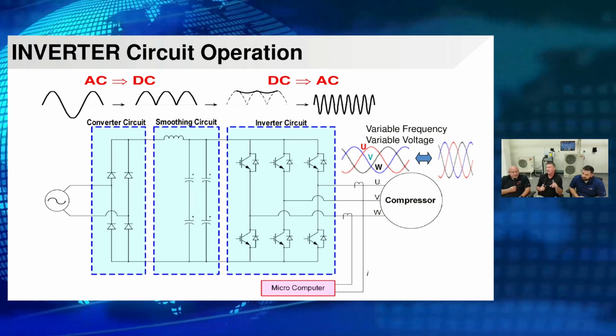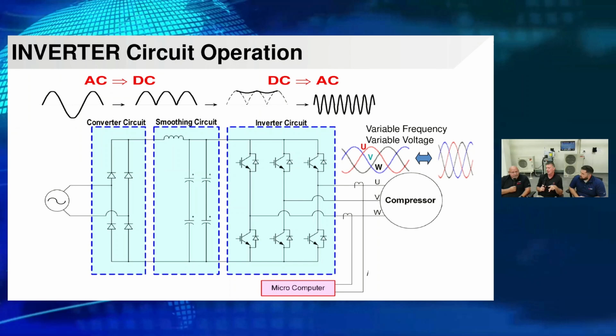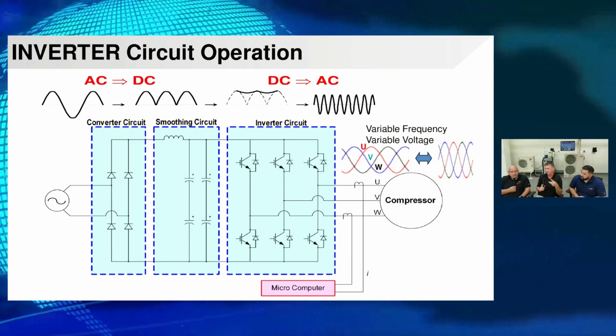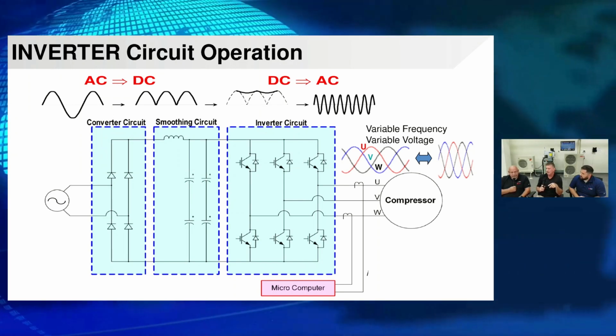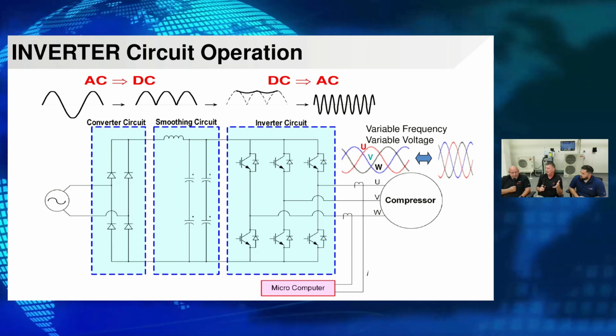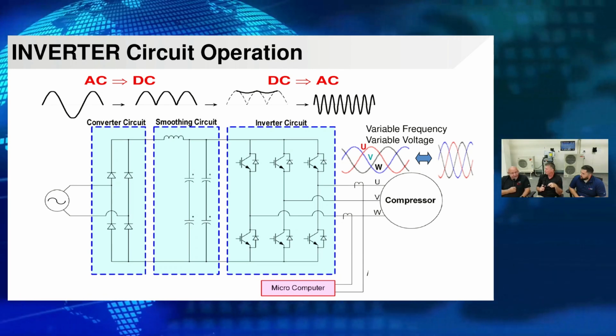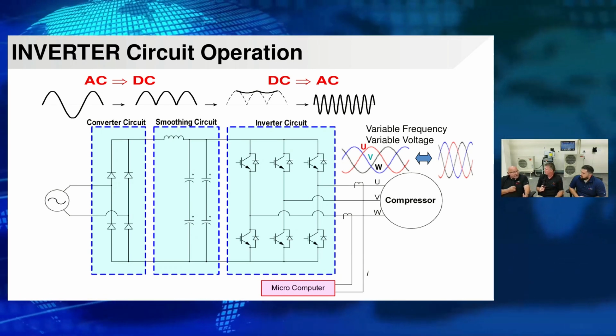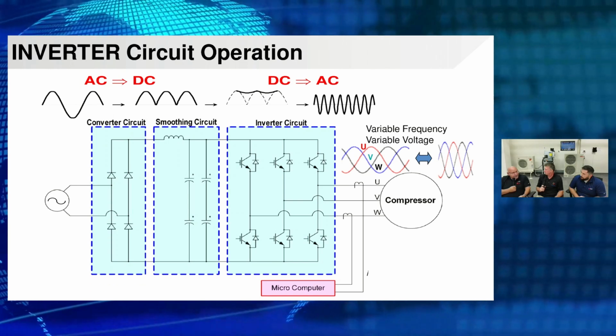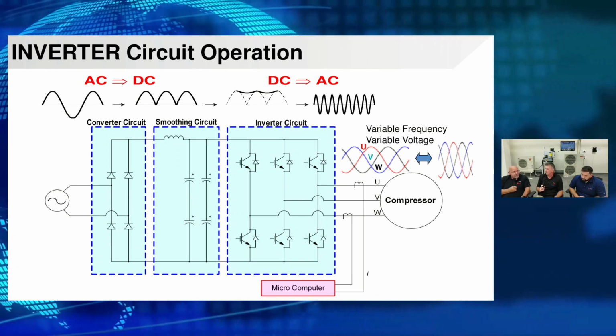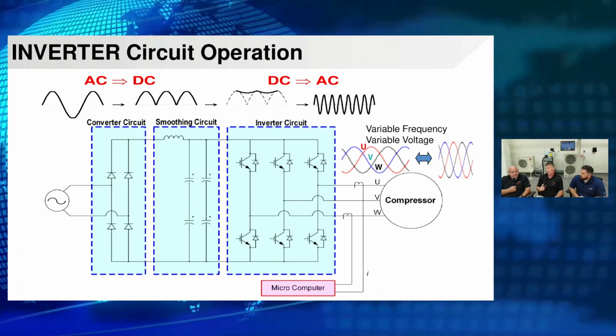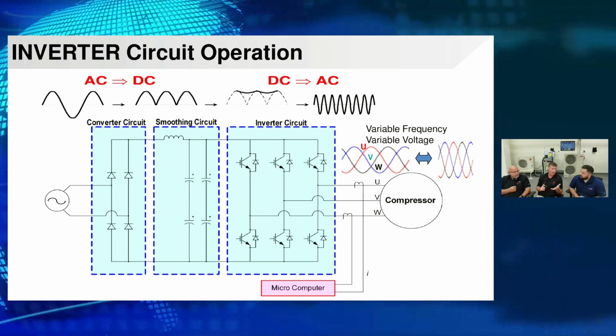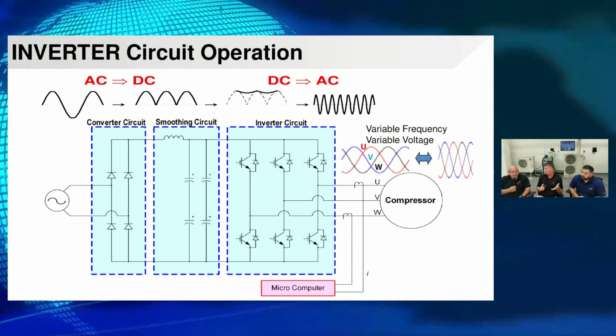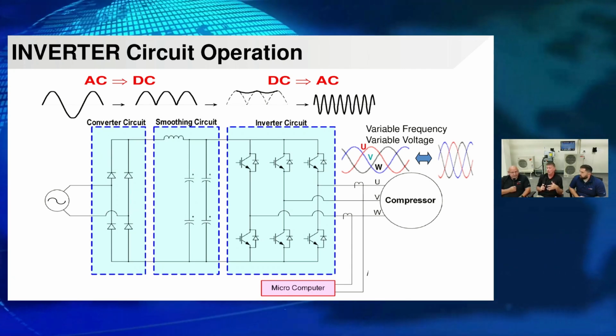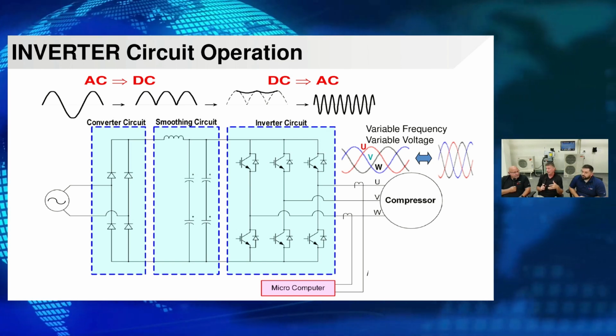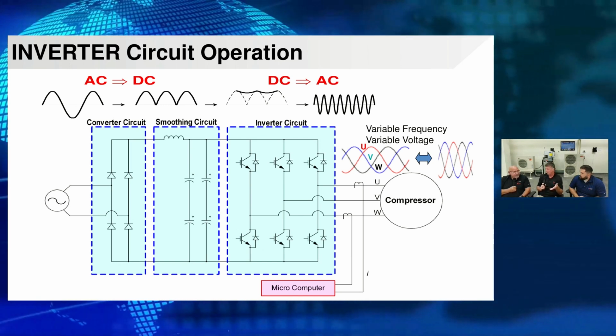Yeah, absolutely. And by utilizing two of those legs, we're actually crossing over those three sets of windings. And so we're getting a combined amperage reading off that motor. Again, back to electricity 101. If one leg is suffering, the other two are going to suffer as well. Absolutely. So now we're able to do a variety of things. We can look at locked rotor. We can look at imbalance of the motor as well. If we know that we have good clean power coming out, but yet we're drawing varying amperage on different legs, we may actually have a winding issue.